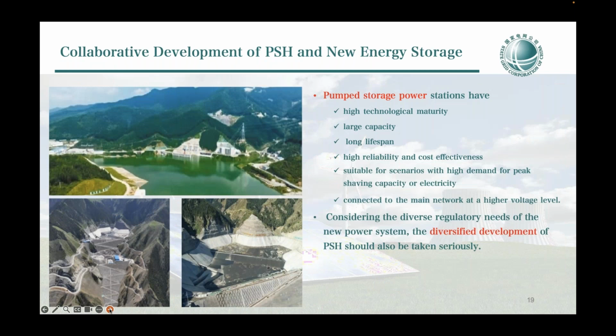Comparing with new type storage, PSH has the advantage of high technological maturity. It has experienced 114 years of development, and PSH can have very large capacity. Generally, a PS station could have 1.2 to 3.6 million kilowatts, and it has a long lifespan, at least 40 years, usually up to 60 years. It also has high reliability and cost effectiveness.